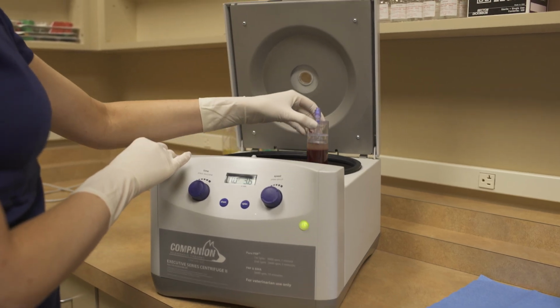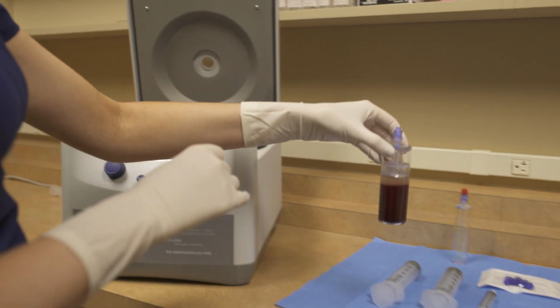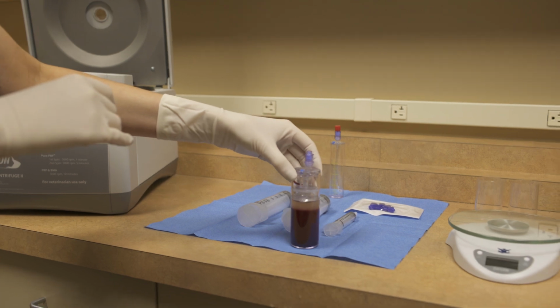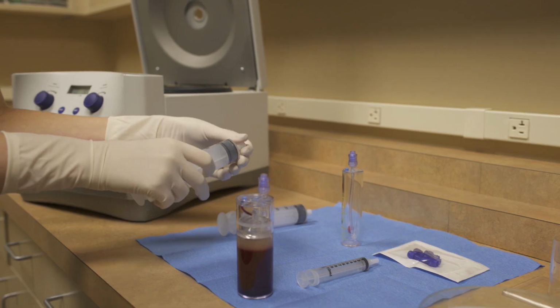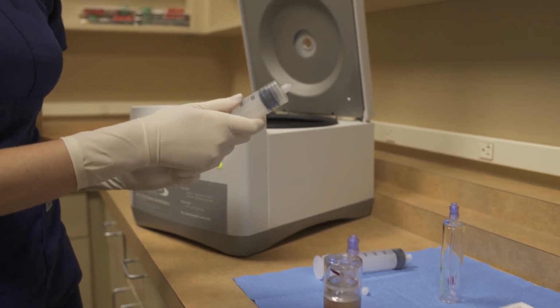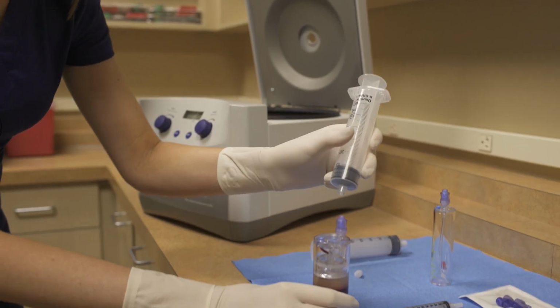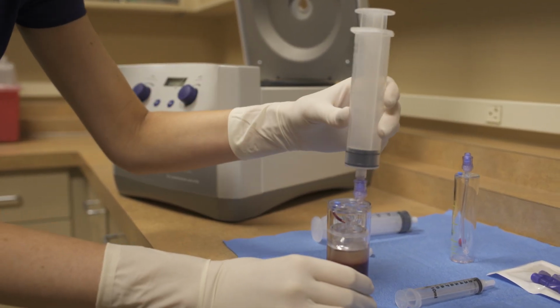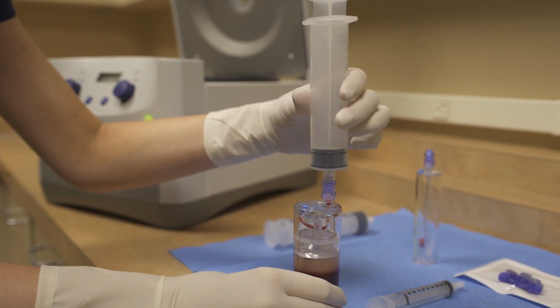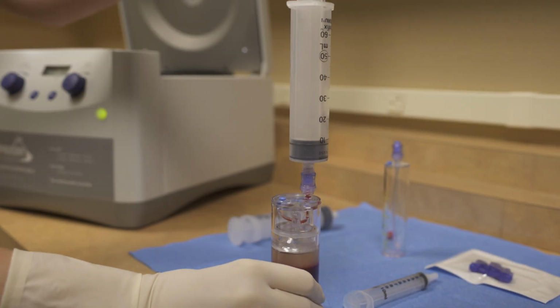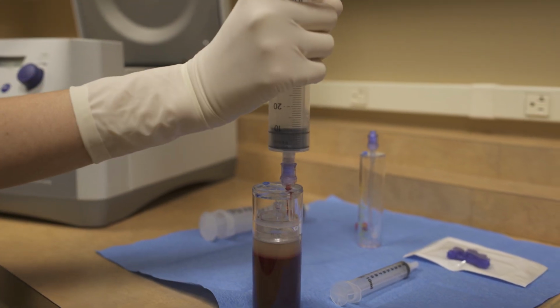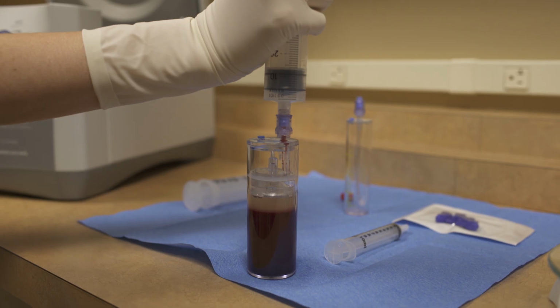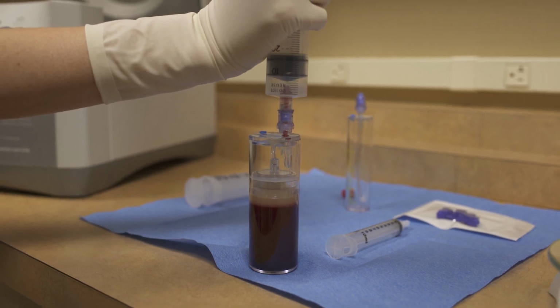Once the spin cycle is finished, which is signaled by the centrifuge lid opening, remove the spun sample from the centrifuge. Be careful not to shake or drop the device, as this could resuspend the cell layers and require an additional spin. Attach a new 60 milliliter syringe to the device. Aspirate the platelet plasma suspension by pulling back on the plunger until red blood cells are seen in the top of the line.